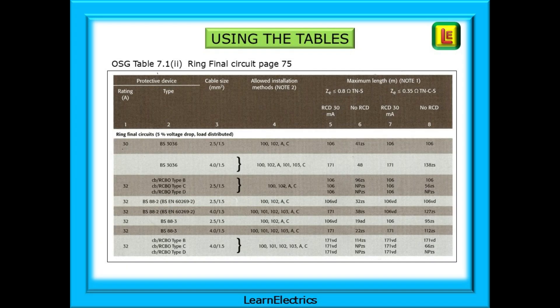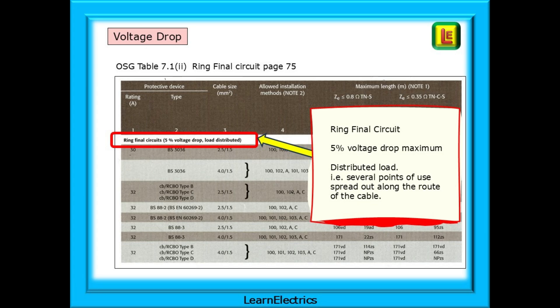Back to Part 7 of the On-Site Guide. We've chosen a 32-amp ring final circuit for this example, so go to Table 7.1.2 on page 75. The table is full of choices. Find the section headed Ring Final Circuits towards the top of page 75. It reminds us that the voltage drop is 5% maximum, which is 11.5 volts for a 230-volt single-phase circuit, and a distributed load - that is to say, several points of use spread out along the route of the cable. The load isn't all bunched up at the end of the circuit.